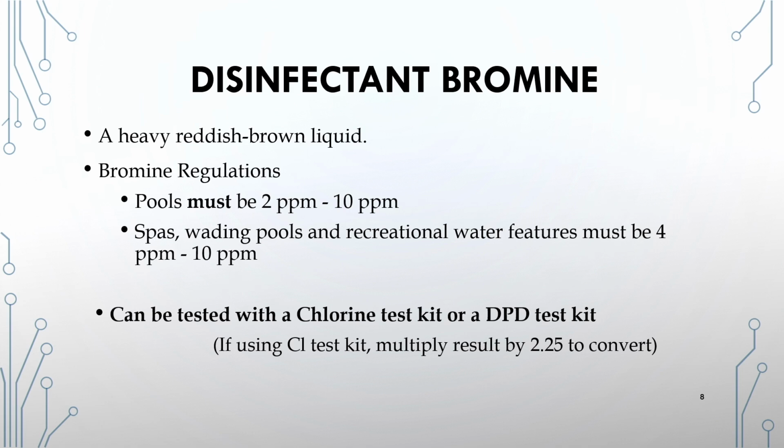Some pool operators enjoy the reduced effect of disinfectant byproducts, including bromamines. Indoor pools that use chlorine may find it necessary to frequently shock the pool to reduce chloramine levels, which can foul the air and cause corrosion to metal items around the pool. Bromine is known to have a less pungent smell, even when combined with ammonia or nitrogen. Combined bromine, or bromamines, also remain a viable, although slightly less potent, sanitizer.